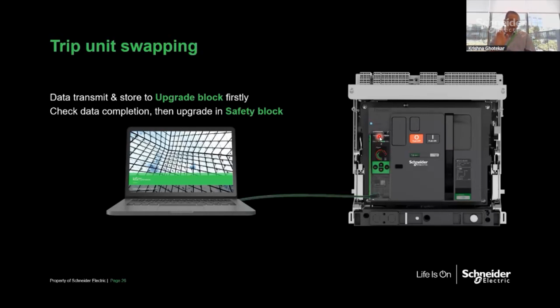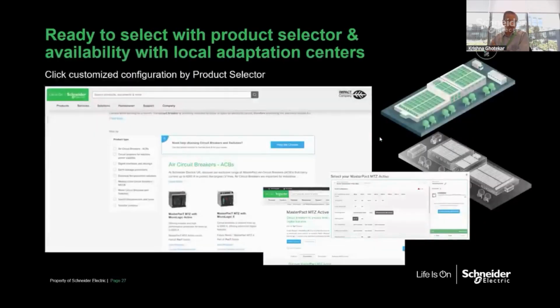Having said that, if you need a switch disconnector, don't just remove the trip unit. It doesn't become a switch disconnector. For that, we have a dedicated HA type breaker as per IEC 60947-3. So as a reminder, a circuit breaker cannot be changed to a switch disconnector. It is a totally different breaker, even for us it comes from the France factory. Or if it's a switch disconnector, it cannot be changed to a breaker. Both are different blocks as per the IEC standards. In terms of manufacturing, they come from the same factory called MasterPact, near Grenoble in France, where we source MasterPact NT NW. The MTZ Active breaker also comes from the same factory.